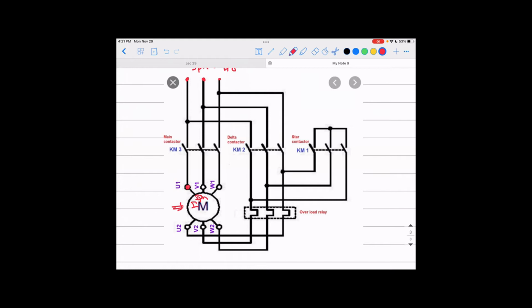Those are the terminals of the machine. So that is phase A terminals, call it U1 and U2, and here is phase 2 terminal. I'm gonna get blue, so that is phase 2 terminals. That's 2 terminals for the phase, and that is the last one, phase C terminals, call it W1 and W2. Okay, so the motor has 3 phases for the stator, and that's what we deal with, and each phase has 2 terminals, 2 points, like you know.